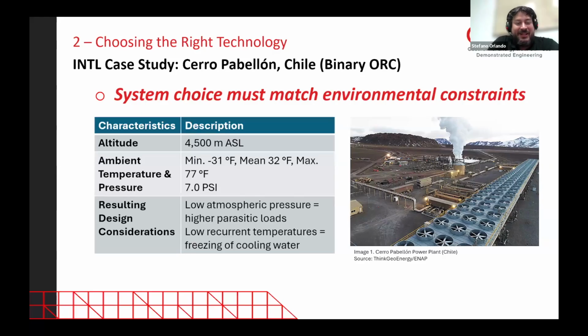So it means that usually it's very cold there, and in the cooling tower we can have issues of icing, freezing of the water, which means issues running the power plant. So someone in Enel had the idea of saying, okay, I will maybe produce a little less, but at least I will always be producing. So let's put an ORC instead of a steam condensing turbine plant. For this reason, now in Cerro Pabellón we find a binary system instead of a steam condensing plant.